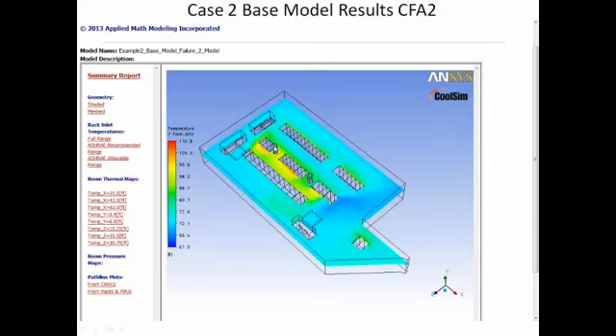Yes, I think there's an opportunity to do that, Magnus. I think with the CFD tools, there is an opportunity to create, model and predict the optimal operating point for any data center using an iterative process. And particularly the way we've set up CoolSim with cloud computing, we did it that way on purpose so that you can run multiple scenarios at the same time to understand which scenario is best for your data center. Now, Magnus, this is true of all data centers regardless of type.